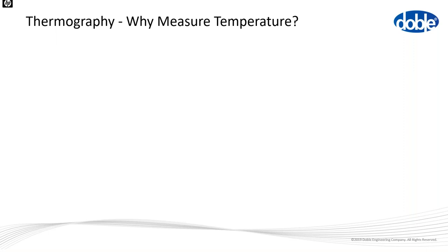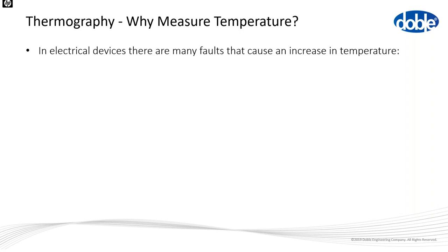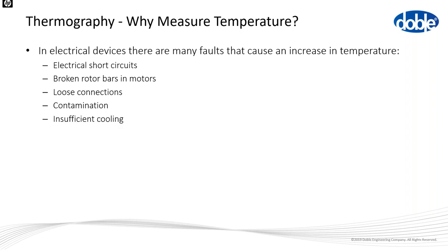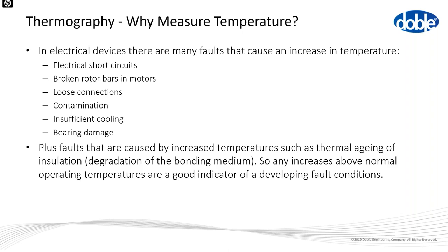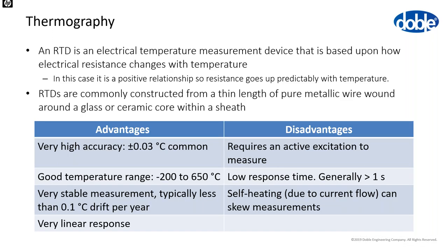Thermography — why measure temperature? In electrical machines, many faults cause an increase in temperature: electrical short circuits, broken rotor bars in motors, loose connections, winding contamination, insufficient cooling, bearing damage. There are also faults caused by increased temperatures, such as thermal ageing of insulation. Increases above normal operating temperatures can be a good indicator of developing fault conditions. For measuring winding temperatures, we typically use RTDs — resistance temperature detectors — based on how electrical resistance changes with temperature, typically constructed from a thin wire wound around a glass or ceramic core within a protective sheath.